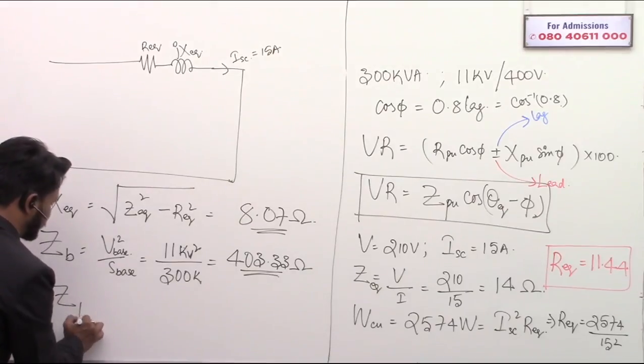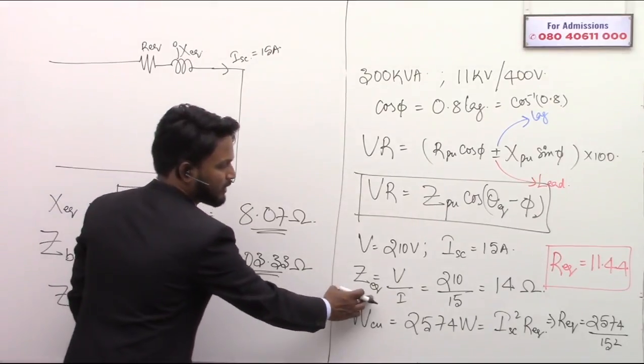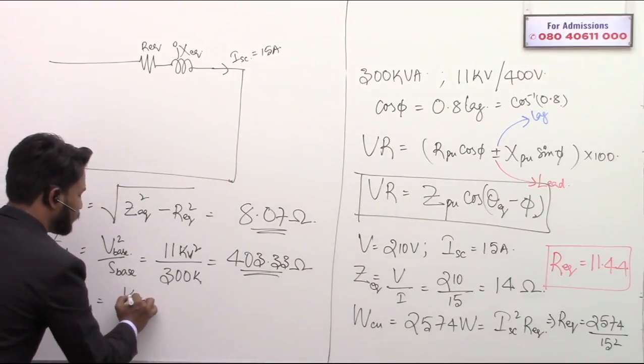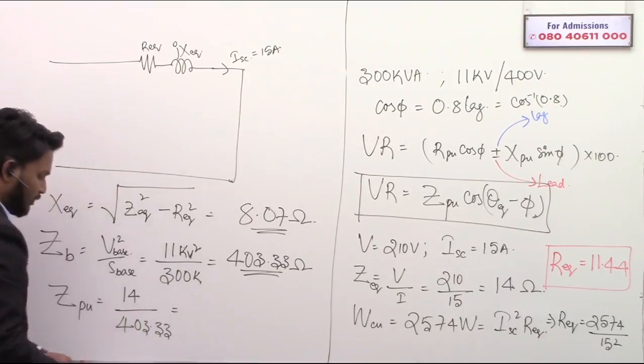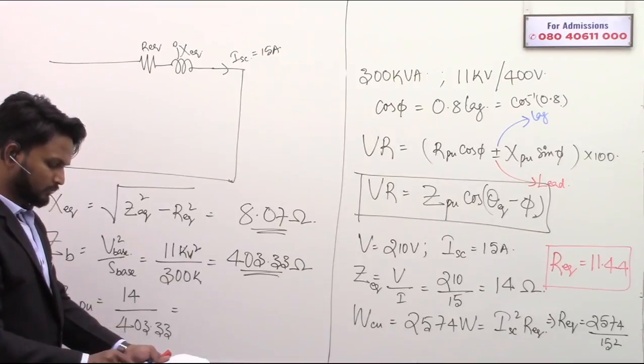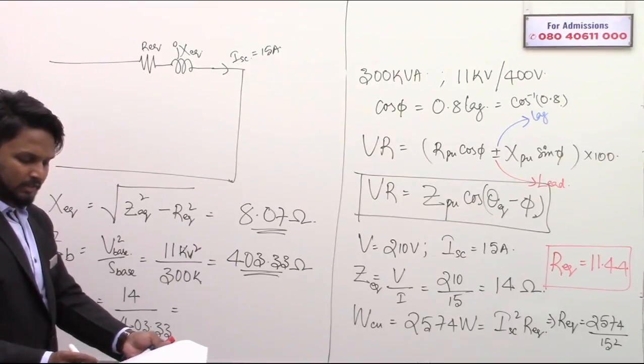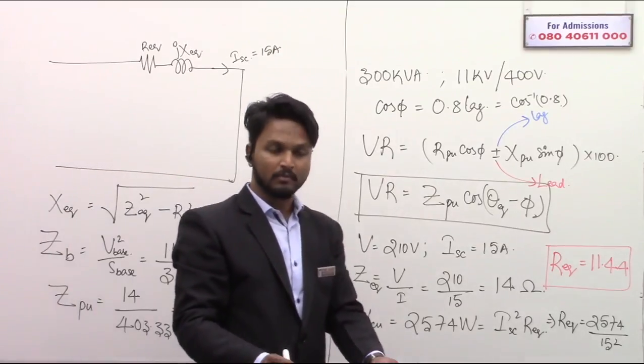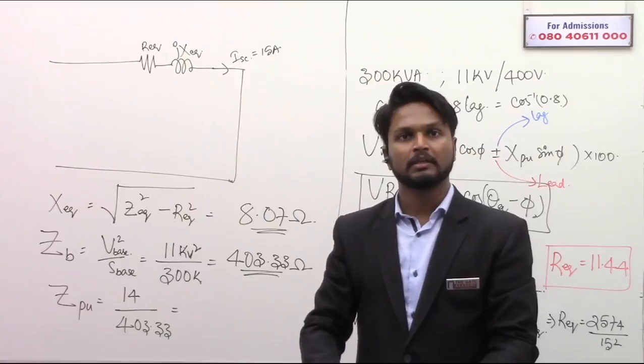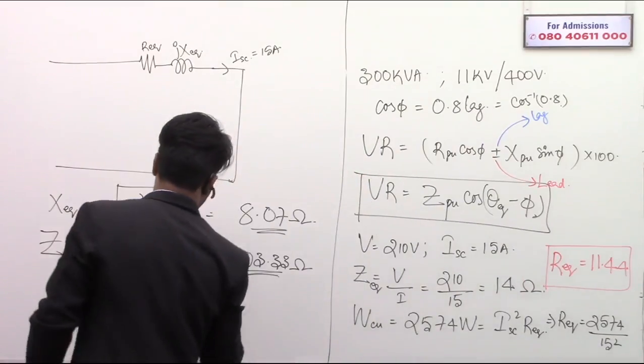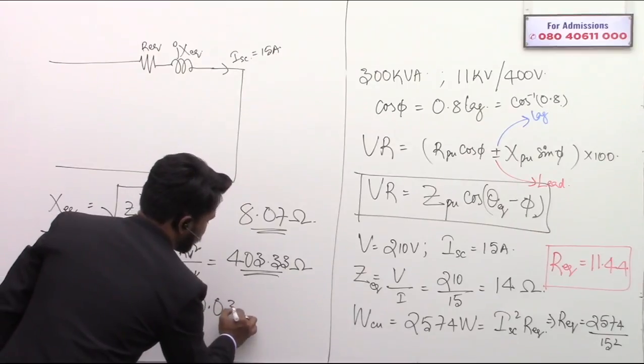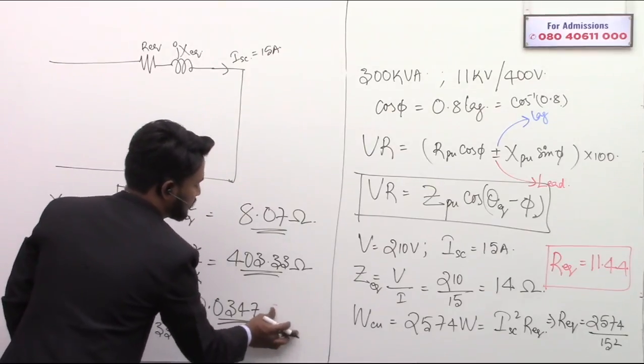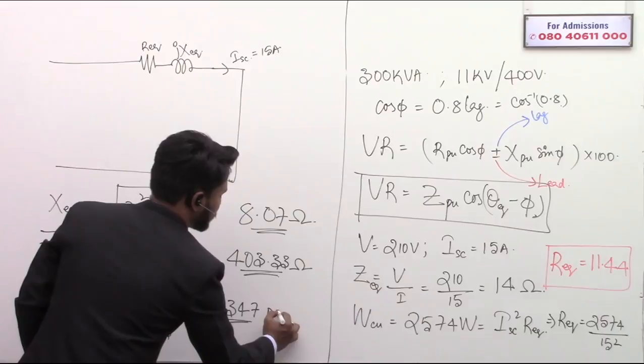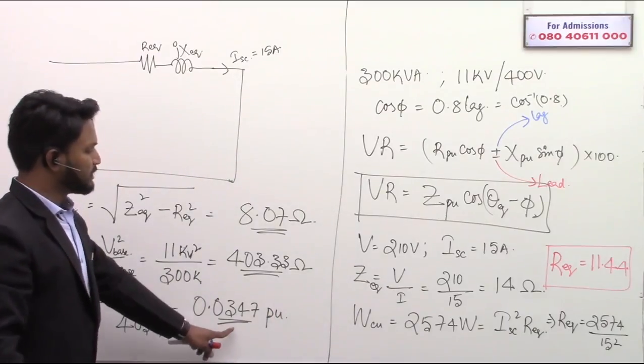Therefore, Z per unit is equal to Z actual. What is the value of Z actual? Actual impedance is 14 ohms divided by 403.33 ohms. So what is the value of Z per unit you are getting? Z per unit is 0.0347. Are you getting the same? Very good, Sri Rama. The value of Z per unit is 0.0347. Sorry, per unit, there is no unit. So this is the value of Z per unit.